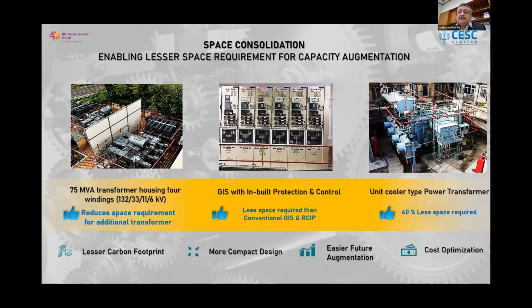The other network element we are currently adopting is 132 by 33 kV transformers with unit coolers. Unit coolers mean the radiators are not there. In the footprint of a 50 MVA transformer, we can install a 100 MVA transformer, which requires very little space, and you can double up the capacity.